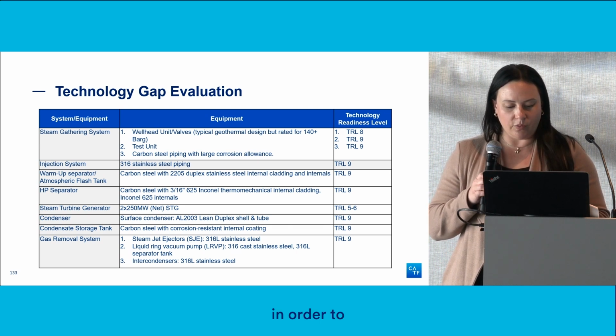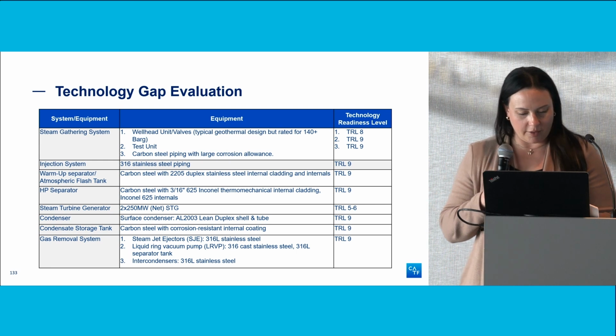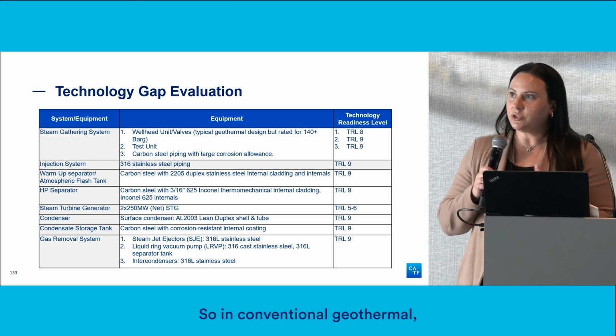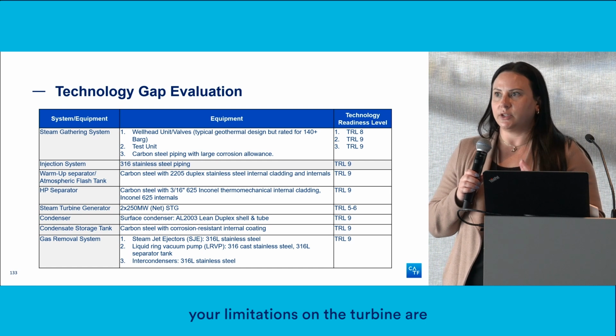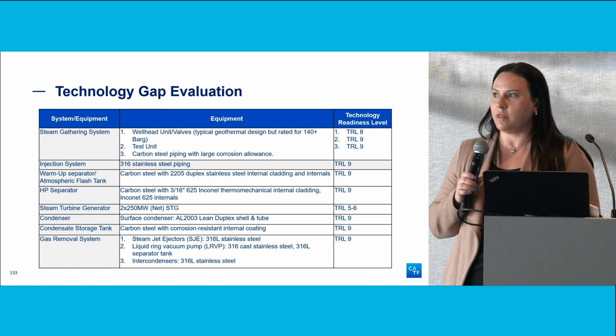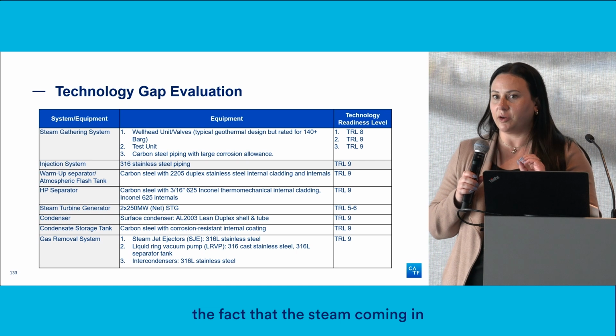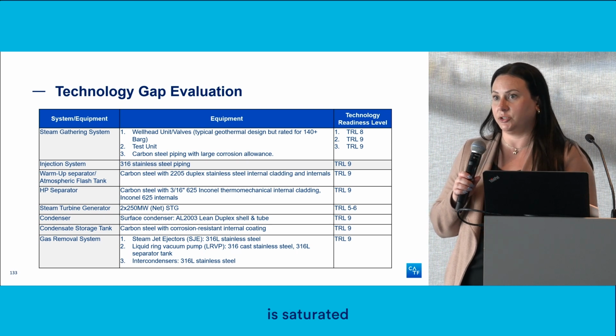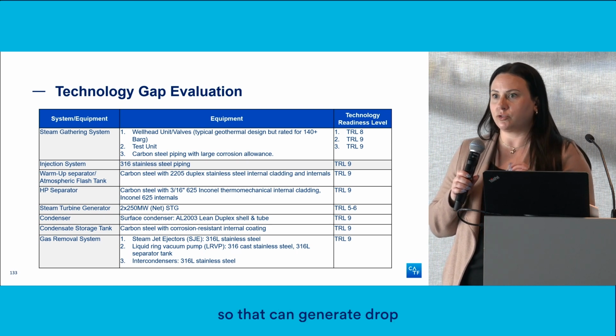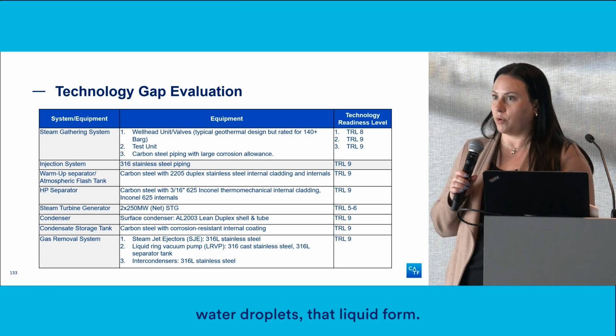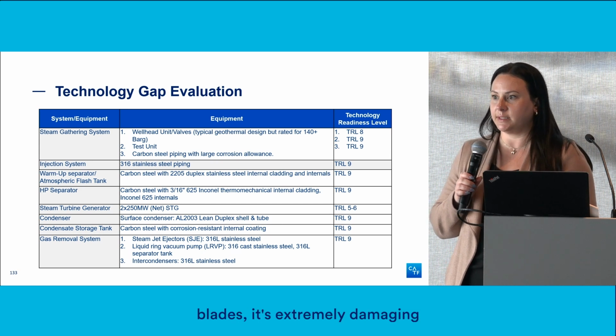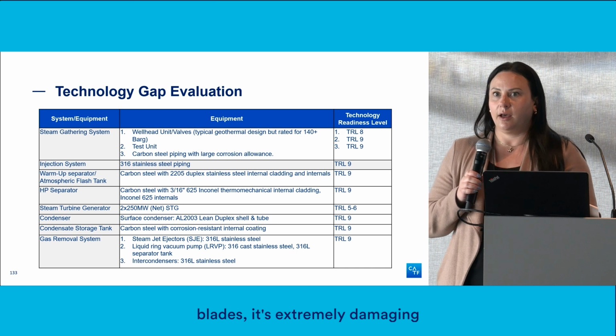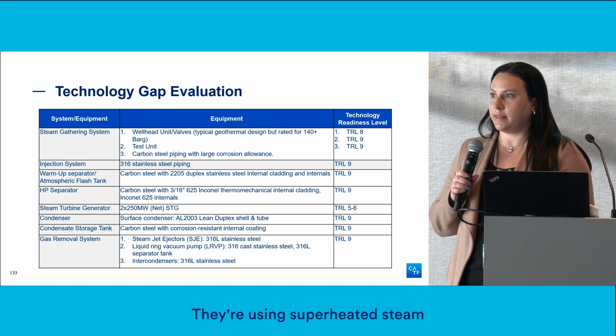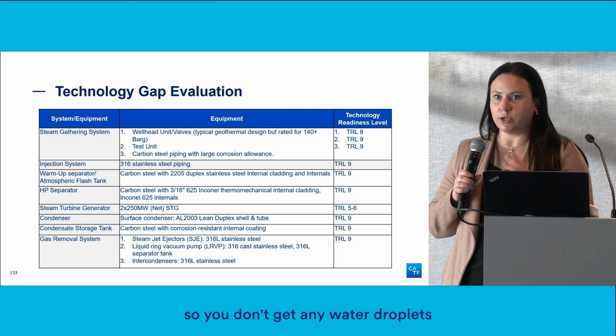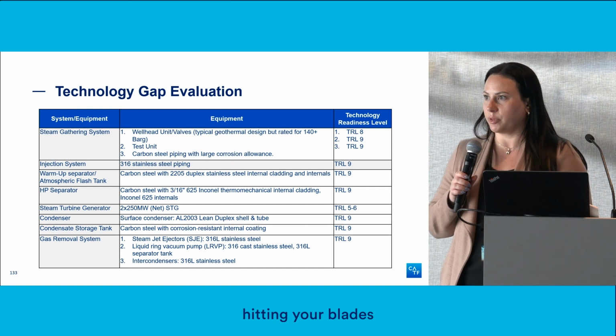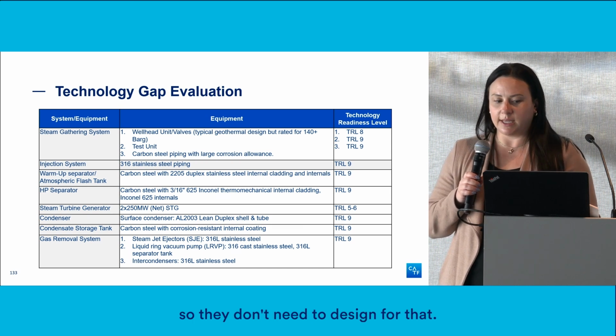In conventional geothermal, your limitations on the turbine are that the steam coming in is saturated, so it can generate water droplets in liquid form. When that hits the turbine blades, it's extremely damaging. On traditional power plants, they use superheated steam, so you don't get water droplets hitting the blades, and they don't need to design for that.